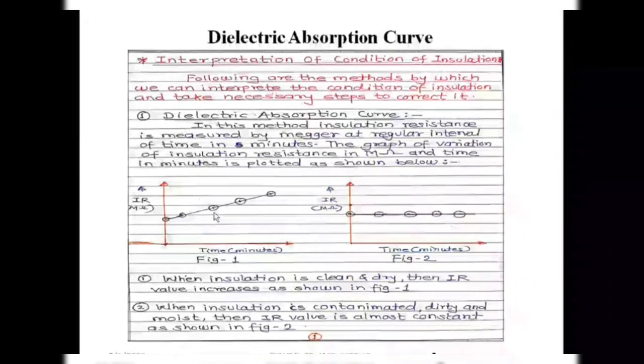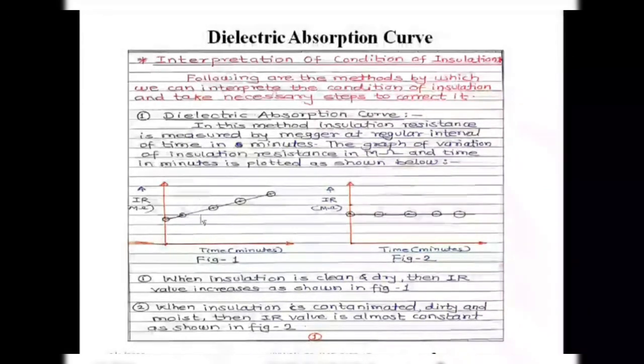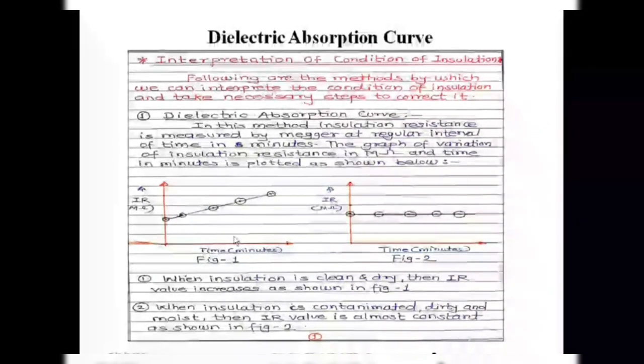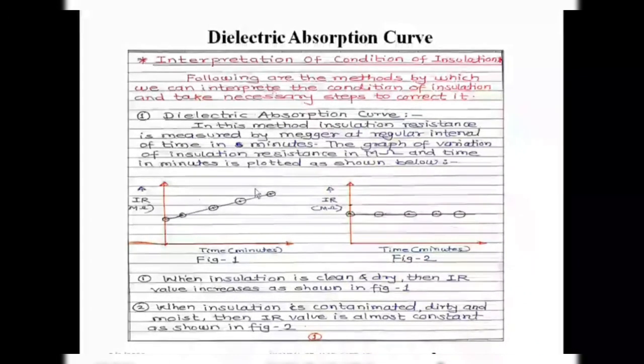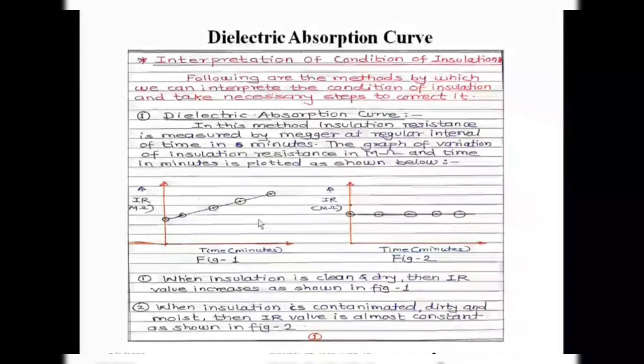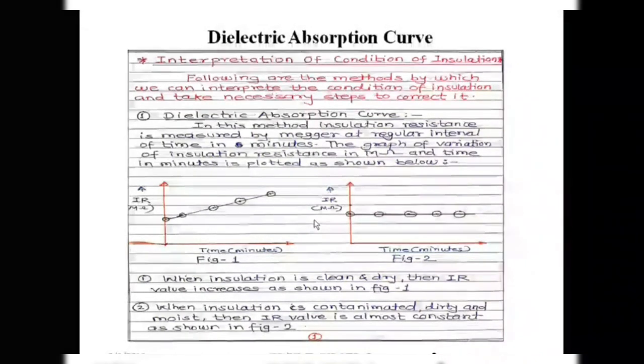The first curve shows that the insulation resistance measured by the megger goes on increasing over the time period. This is figure number one. If we get this graph from the test, then the condition of insulation is concluded to be clean and dry — the insulation does not contain any moisture or any kind of impurities, so it is in good condition.